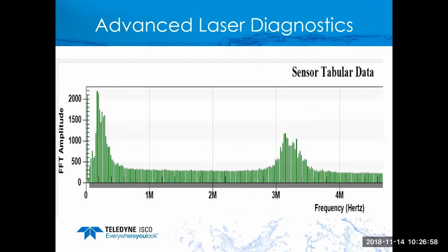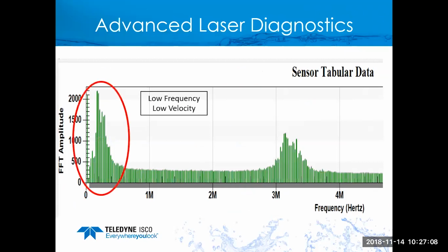So we looked at it, and here is the diagnostic that we got back from this site. And you remember the other one I showed you, it was a very nice, clean one. This is not so clean. And the reason is we're getting low frequency, low velocity on the far left of the spectrum. And really what we want to see is this. This is our real velocity over here. So with the laser now, we've been able to make some adjustments so we can, for lack of a better word, tweak it to say ignore anything left of whatever velocity we want. So that's what we did in this one. We just told it, hey, we're seeing these low frequency velocities, probably due to entrained air, big air bubbles on the top, could be turbulence, swirling, and all that. But we went ahead and set the laser so that we could ignore that.